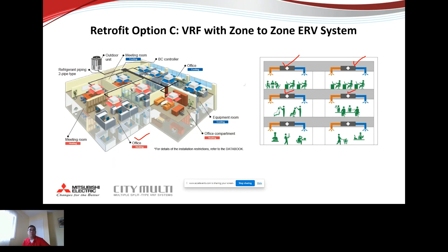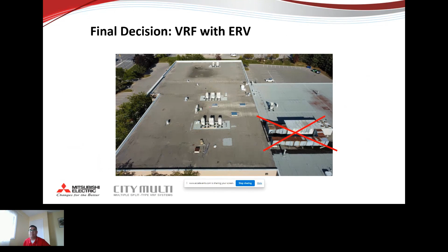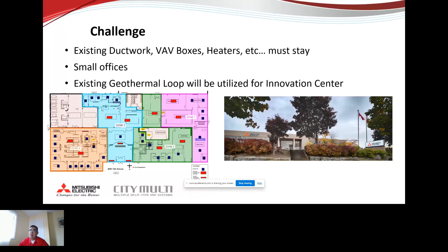So for example, for the cafeteria in our office, the occupancy at 9 a.m. or 10 a.m. and the occupancy between lunchtime and 3 p.m. is usually very, very different, right? So we are able to have that kind of reactive solution to provide ventilation, fresh air, heating and cooling. So the final decision is really the VRF system that you can see over here, between a rooftop unit and the VRF condenser. But it does come with some challenges, because we want to have minimum disturbance for the ductwork, existing equipment, and small offices, and we still want to utilize the geothermal system. Therefore, we are using VRF technology to have heating and cooling at the same time.